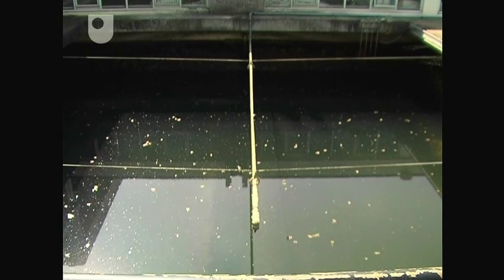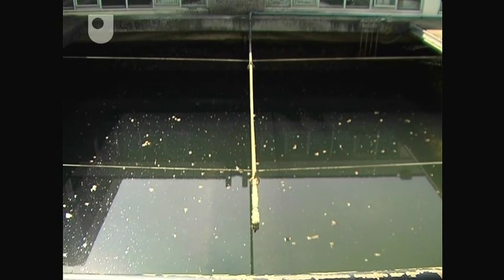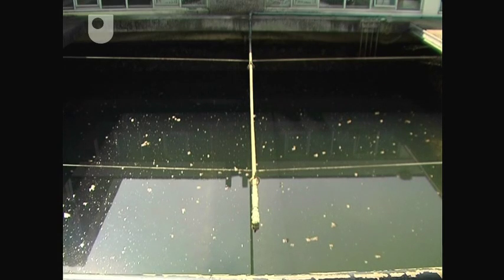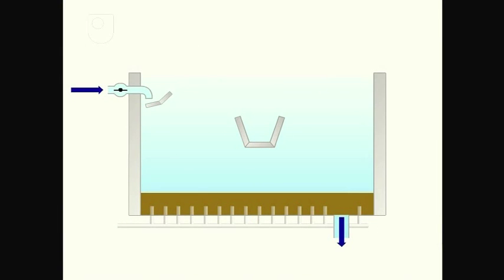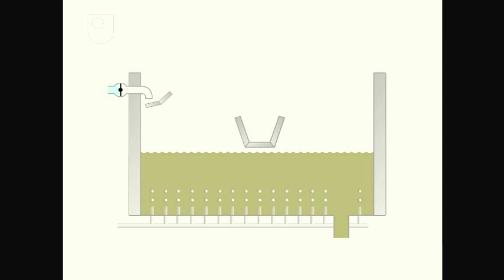When the sand is choked full of solids, the filters stop working and so they're backwashed. Backwashing comprises five stages. First, the water flowing into the filter is stopped and consequently the water level drops.